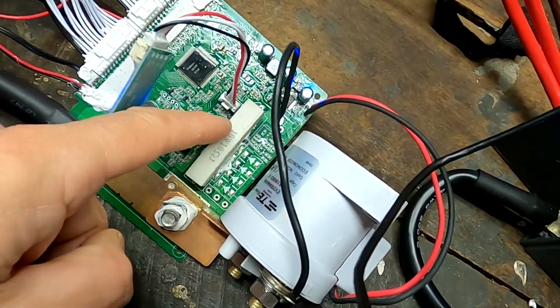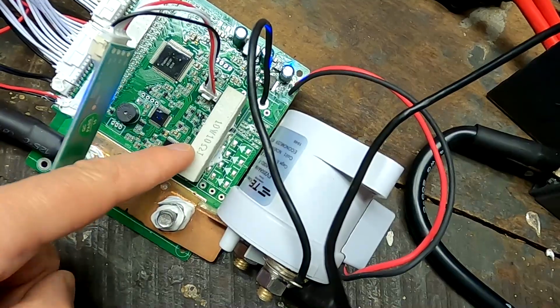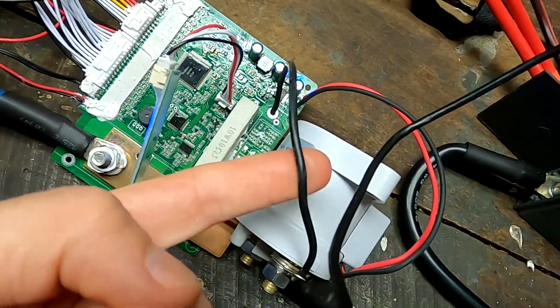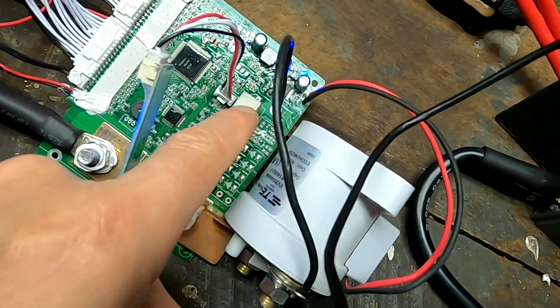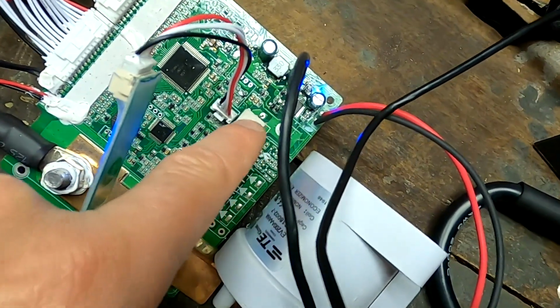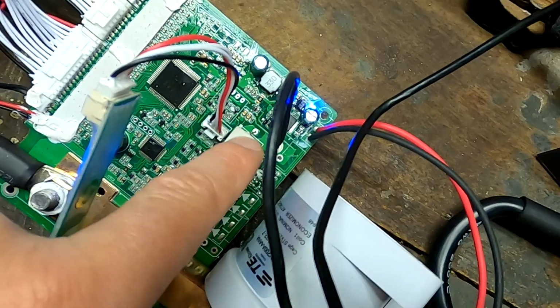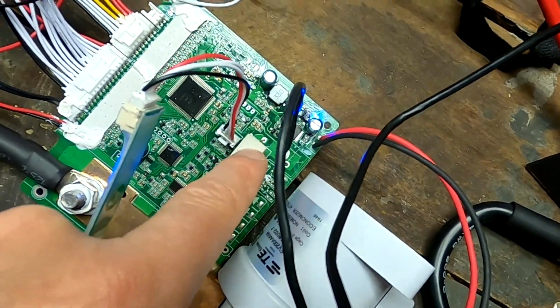Interestingly, this 10 watt 10 ohm resistor here is in series with this one. But there's more connected, not only the resistor. They are connected on the PCB here with two other devices which I cannot identify where they are going to. So obviously this is the pre-charge resistor. When we have load connected like inverters, before it turns on the relay, it pre-charges these capacitors. Otherwise you would have a very high inrush and could melt the contacts of the relay.